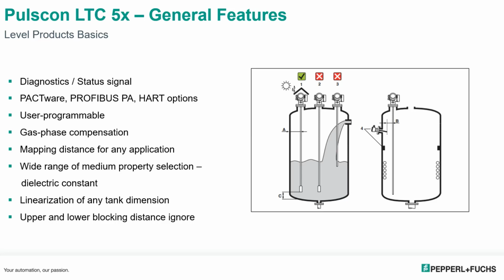You can map out the distance, like if there's a ladder inside there or something interfering with the signal, you can map that out so it ignores it, but it will detect the liquid. They can linearize the tank dimension, so if it's a cylindrical tank on its side, you can make that a linear signal output according to the gallons or liters inside the tank.